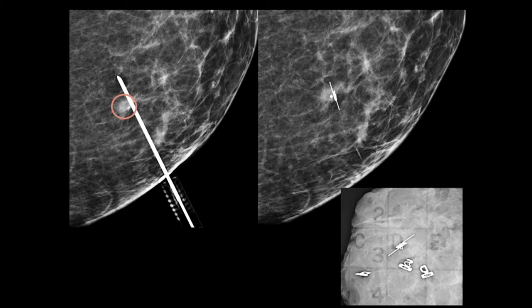Once the SAVI SCOUT reflector is deployed, the surgeon uses a handpiece transducer to localize the reflector in the OR. The handpiece transducer emits an infrared light, which is taken in by the reflector, and a signal is generated, reflecting back to the transducer, helping to localize the reflector.